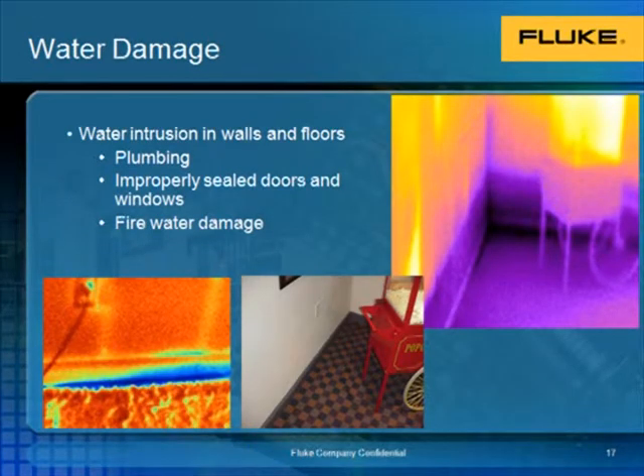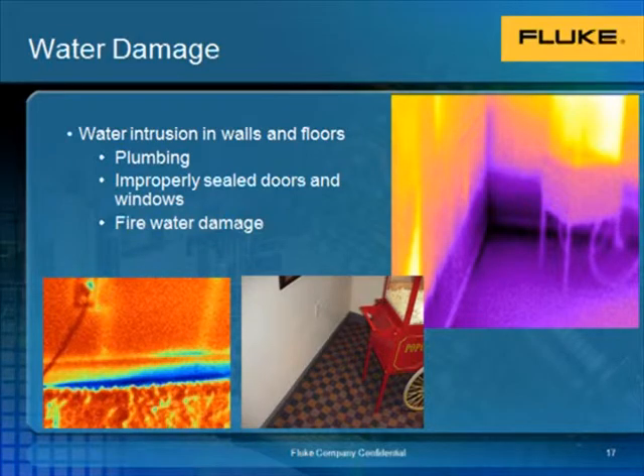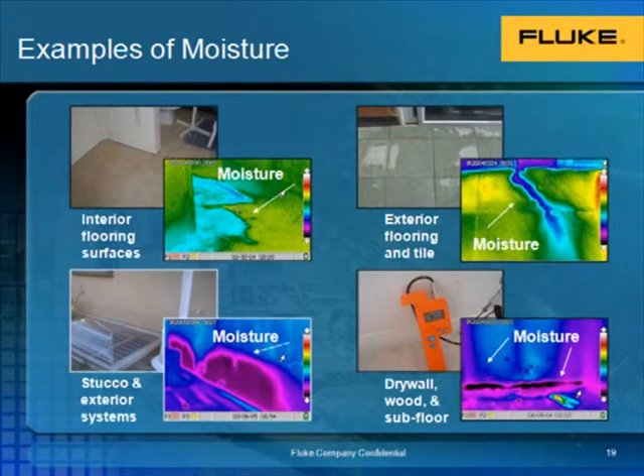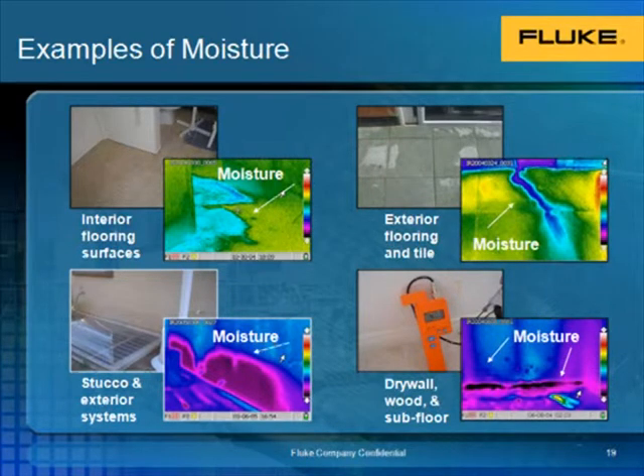Here's another example of water damage within a home. The image in the upper right is of a basement that has recently flooded. Even though there may have only been an inch or two of actual standing water, the sheetrock and insulation has soaked up that moisture about a foot or two up the wall. By using the thermal imager, we can easily see how far up the wall we have an issue. We also see examples of both interior and exterior moisture, and a moisture meter being used to validate the findings. Utilizing the moisture meter combined with the Fluke IR Fusion gives you all the visual verification you need.